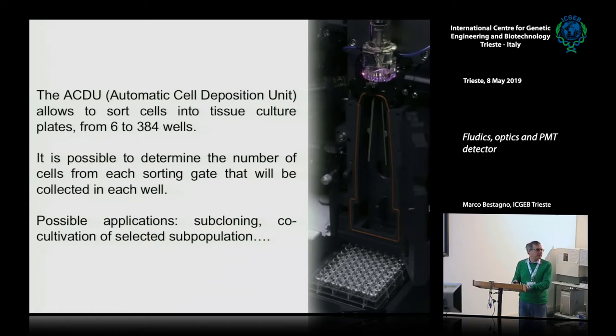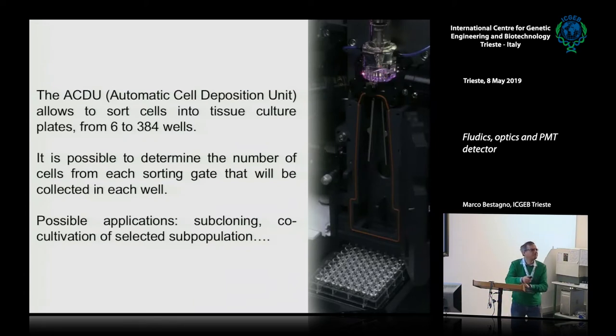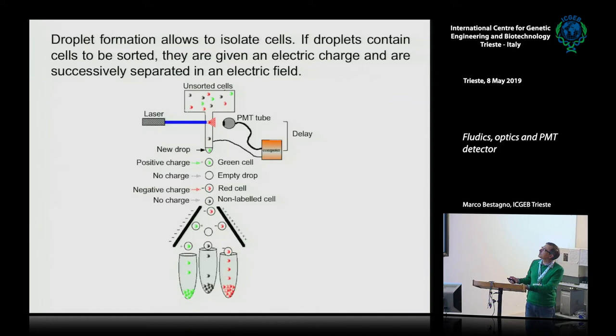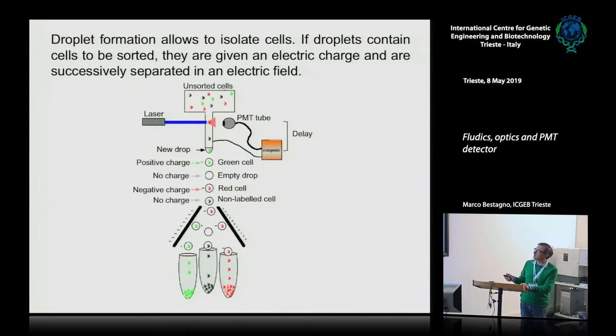From the Q&A: a question was asked about how the droplet gets charged. The answer is that an electric wire connected to the stream formation delivers an electric pulse from the computer when a signal is detected that corresponds to the set parameter. The charge is given to the droplet as soon as it is separated from the stream, and this charge stays with the droplet, allowing the cell to be deflected and separated.